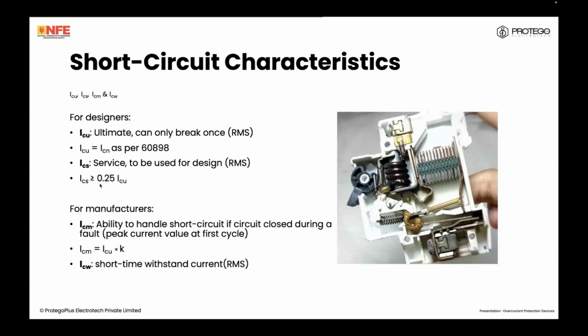Now, the point is that for certain devices, the value of ICS is significantly lower than the value of ICU. So maybe it is 0.5 or 0.75. We need to take this into account, because if a manufacturer tells us that the short circuit breaking capacity is, say, 35 kiloamperes, it may very well be, 35 into 0.25, that the device is only rated to interrupt 8.75 kiloamps under continuous service. So for design, the ICS value is important.